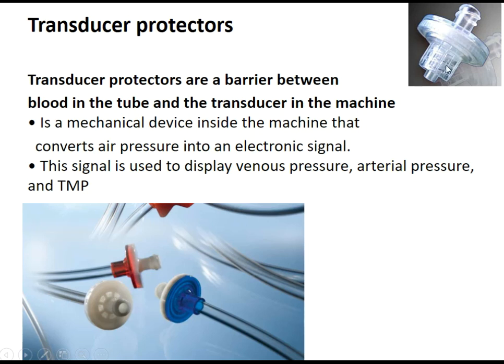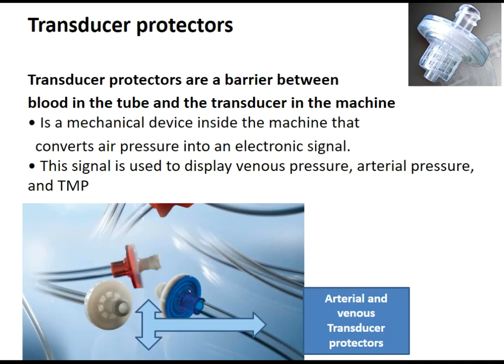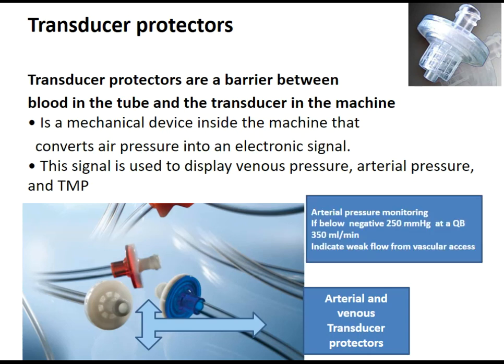The transducer protectors act as a barrier between the blood in the tube and the transducer in the machine. It is a mechanical device inside the machine that converts air pressure coming from the blood circuit into an electronic signal. This signal is used to display venous pressure, arterial pressure, and to calculate transmembrane pressure. Arterial pressure monitoring below negative 250 mmHg at a QB of 350 mL/min indicates weak flow from the vascular access.